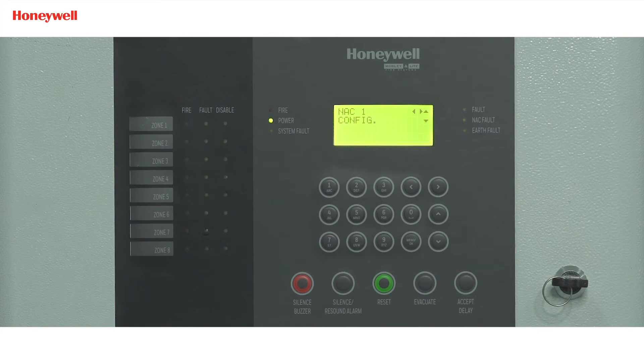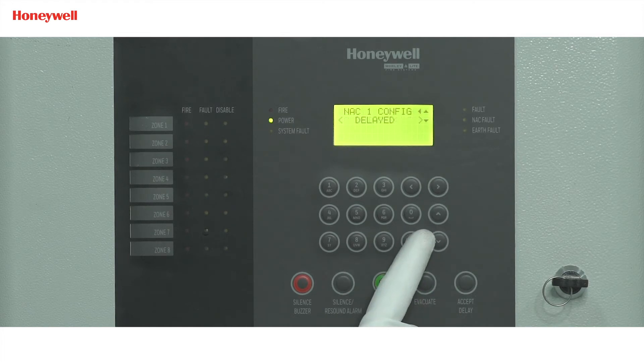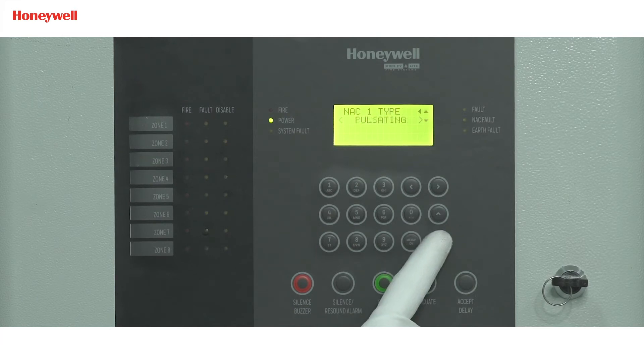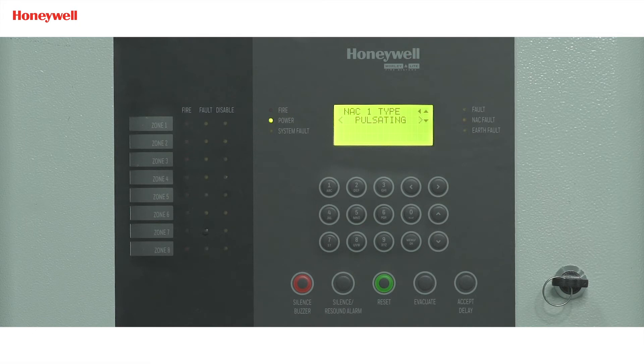After selecting NAC1 by pressing the forward arrow button, we can program it as delayed, not delayed, continuous, or pulsating by pressing the forward arrow button. If delayed is selected, NAC will activate after the programmed delay time. If not delayed is selected, NAC1 will get active immediately. If continuous is selected, NAC1 will give a constant 24 volt DC output. If pulsating is selected, NAC1 will not give a constant voltage — it will be in pulse form.